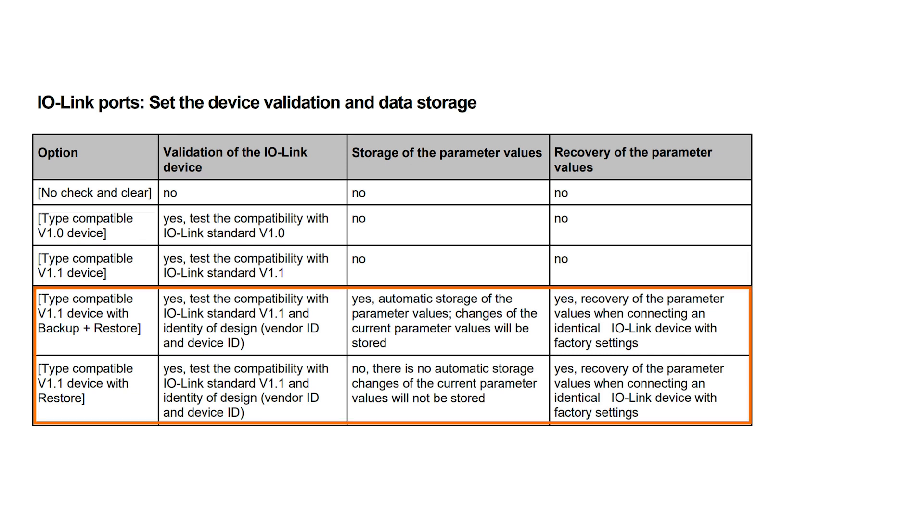The validation check for the new IO-Link Standard 1.1 can be extended by the data storage options, Restore, or Backup and Restore. The Restore function saves a parameter set once and automatically transfers it to a new device with factory settings. The Backup and Restore function also saves any parameter changes made in the meantime. As soon as a new device with factory settings is connected, the saved parameter set is transmitted.